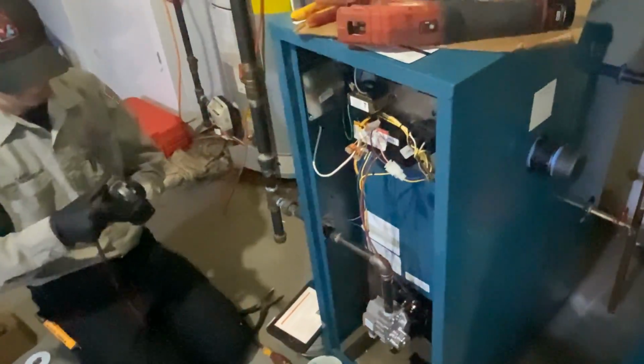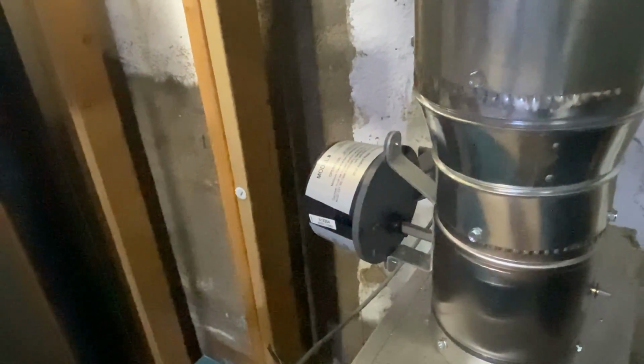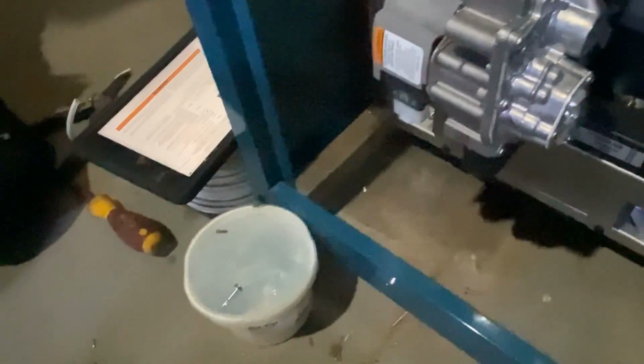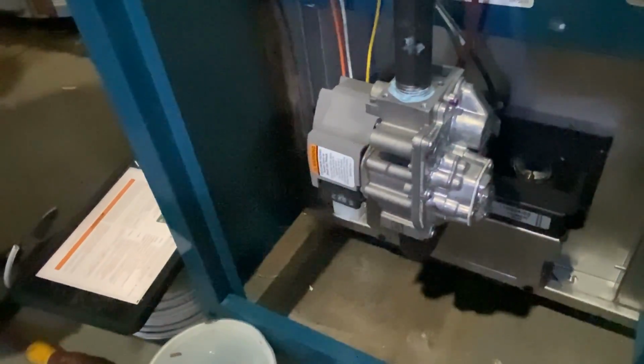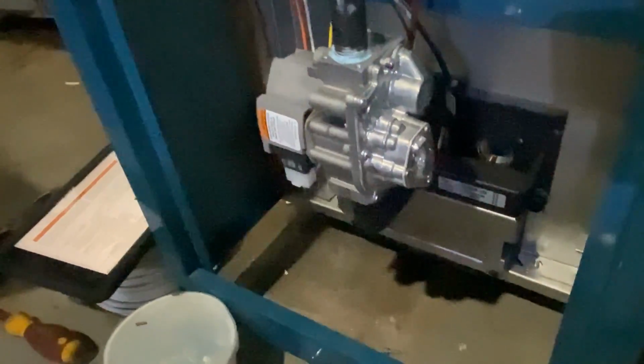All right, so we just got our thermostat call. One of the first things we're going to hear is our thermostat really is going to click. And then our vent damper is going to open. And then we have a click of our gas valve, followed by 24 volts, which is opening that gas valve. And now we have the tick, tick, tick, tick. We may time out because I don't know if Daniel got any of the air out there. He didn't. So, yeah, we're going to time out there.